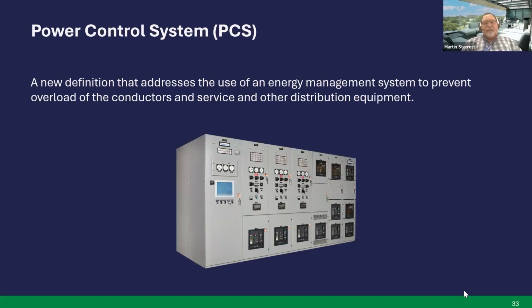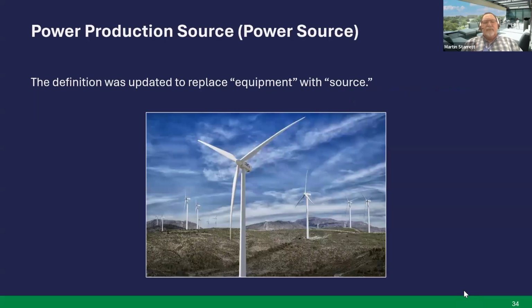Power control system. It's a new definition that addresses the use of energy management systems to prevent overload of the conductors and service and other distribution equipment. So we have energy management systems, but they have now been broken down, and the overload portion of those will be the power control system. That's one of the big things, and we'll be seeing this when we talk about Article 120 a little later. Next slide.